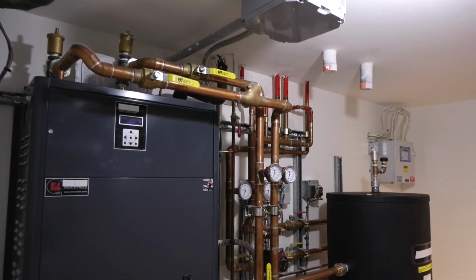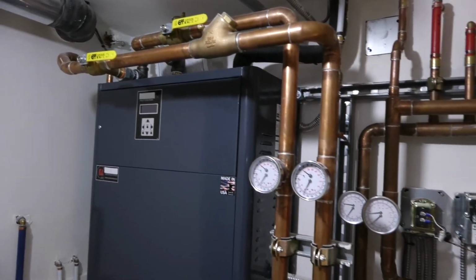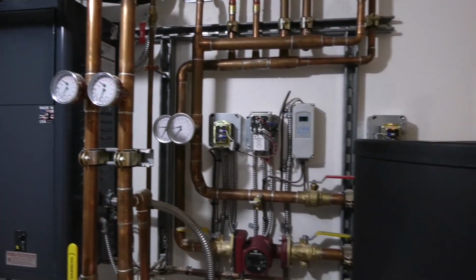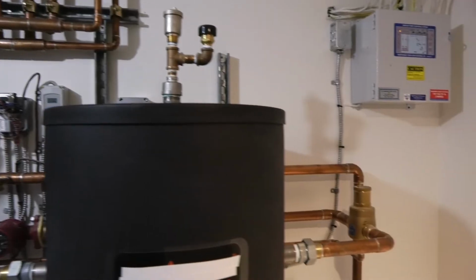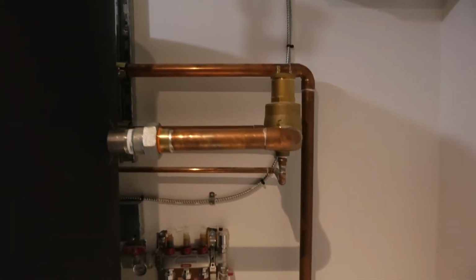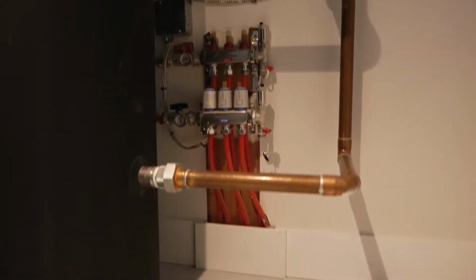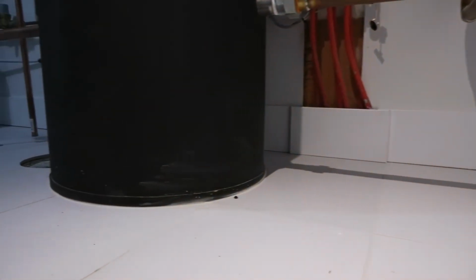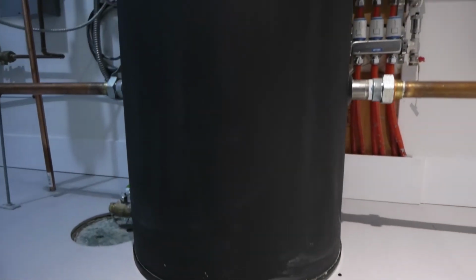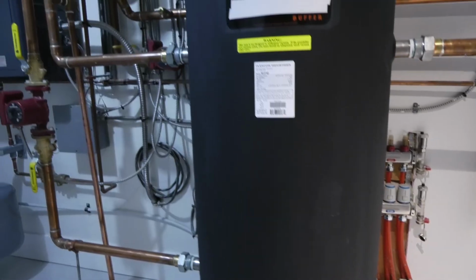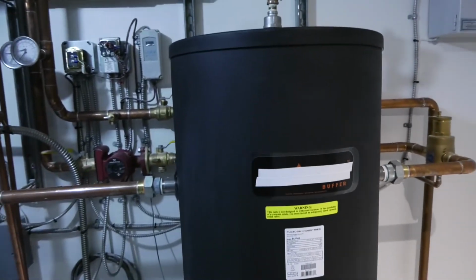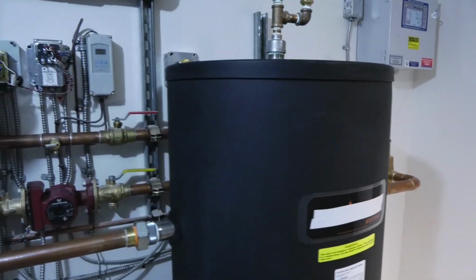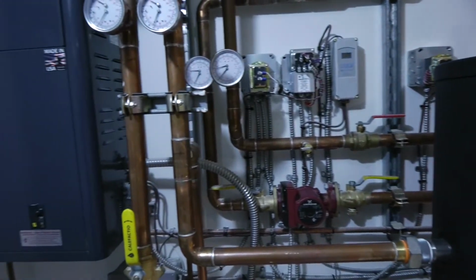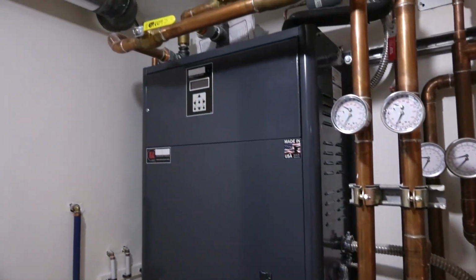So if I had a system that needed 120 degrees Fahrenheit on a design day to heat it, and now I've put another heat transfer spot between the heat source and the load, well, now I'm running my heat pump even hotter to deliver that 120 on the load side. So that heat exchanger, if you've sized it correctly, is probably going to be pretty expensive. It's going to need a lot of surface area to transfer heat at a fairly low delta T.